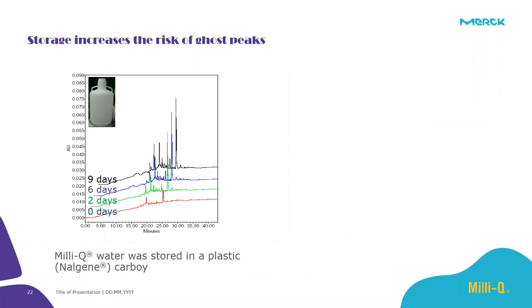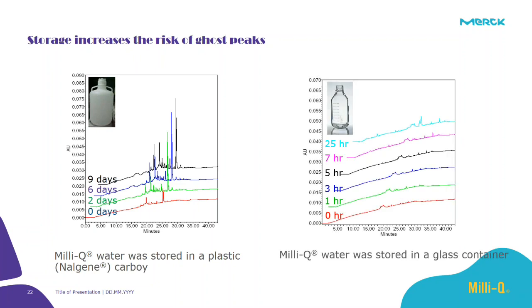So the storage of purified water will increase the risk of ghost peaks. In this graph, you will see the Milli-Q water which was stored in a plastic Nalgene carboy for a long time. On the other hand, you will see the fresh Milli-Q water stored in a glass container. And you will see the difference yourself in the baseline. On the left side, you can see many ghost peaks because of the storage of the water. As my colleague Ahmed explained earlier, pure water should be freshly prepared before the analysis itself. And that's what our Milli-Q systems are providing to you. It's providing ultrapure water or deionized water on demand.